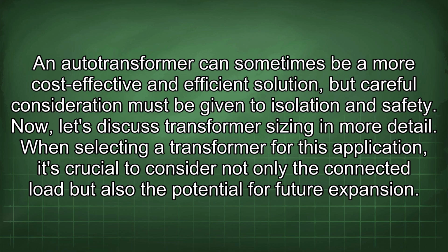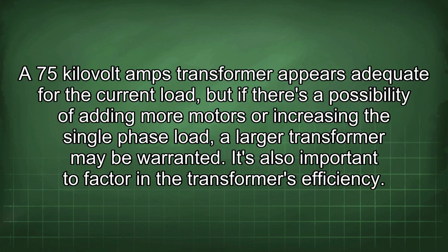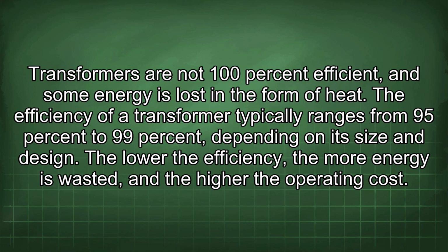When selecting a transformer for this application, it's crucial to consider not only the connected load but also the potential for future expansion. A 75 kVA transformer appears adequate for the current load, but if there's a possibility of adding more motors or increasing the single-phase load, a larger transformer may be warranted. It's also important to factor in the transformer's efficiency. Transformers are not 100% efficient, and some energy is lost in the form of heat. The efficiency of a transformer typically ranges from 95% to 99% depending on its size and design. The lower the efficiency, the more energy is wasted, and the higher the operating cost.